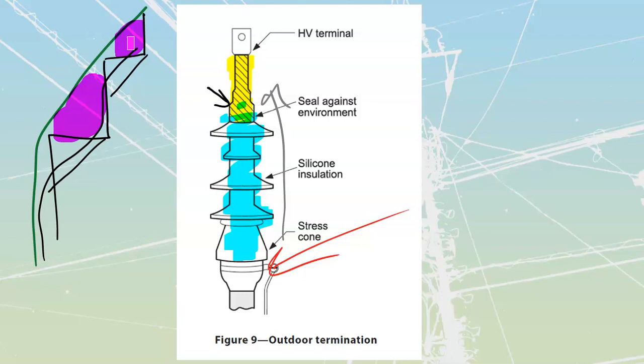Be careful as well when it comes to the high voltage connection. Make sure you remove that strand shield before you crimp this thing on, because if you leave the strand shield on there, it's not going to be as good of a connection, which means you're going to develop heat, leading to breakdown inside here.